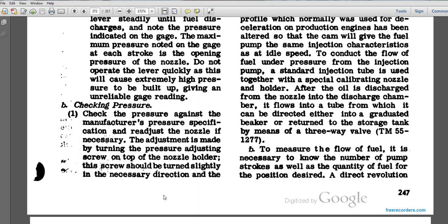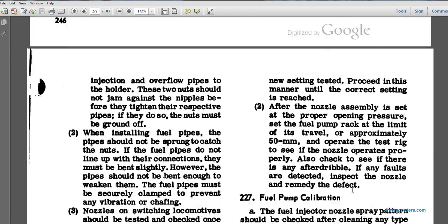Check the pressure against the manufacturer's pressure specification. Readjust the nozzle if necessary. The adjustment is made by turning the pressure adjusting screw on the top of the nozzle holder. The screw should be turned slightly in the necessary direction. The new setting is tested, proceeding in this manner until the correct setting is reached.